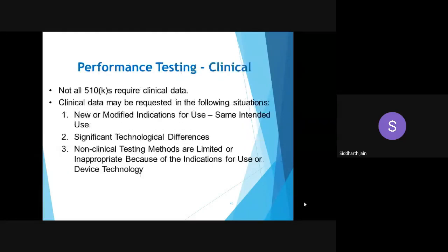As I talked about clinical testing, not all 510Ks require clinical data. If you have the same intended use as the predicate device and there are significant technological differences, only in that case are you required to go for clinical data or clinical testing for your products.